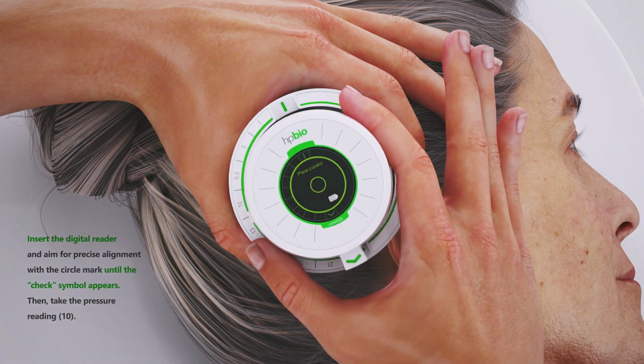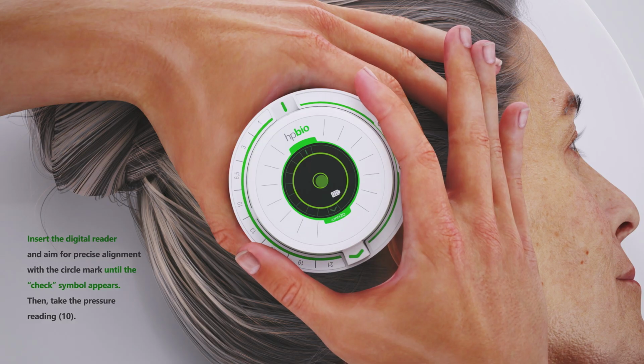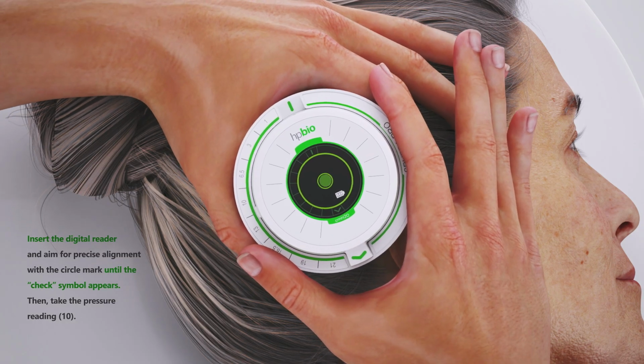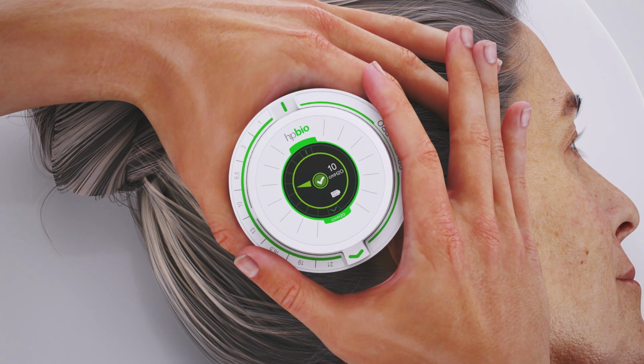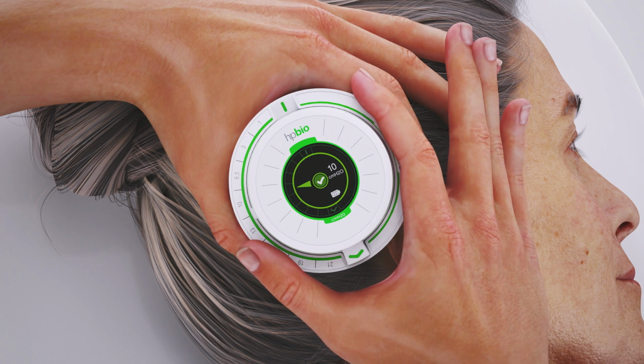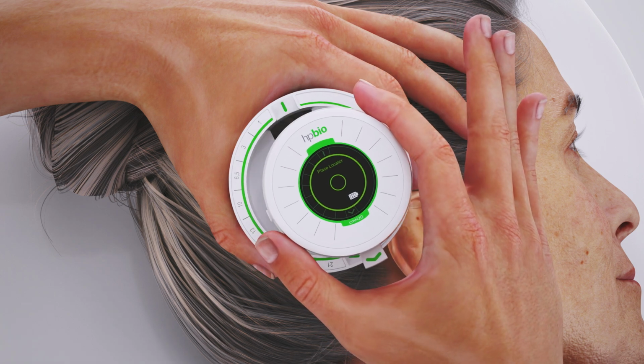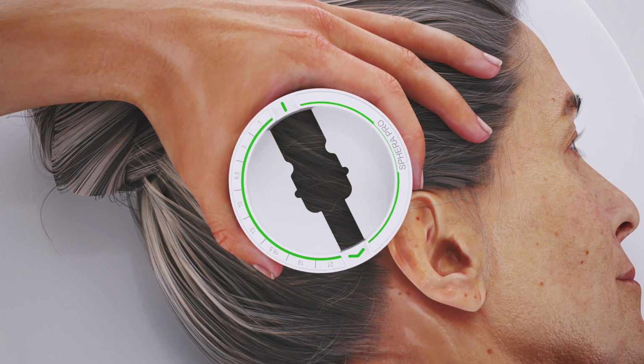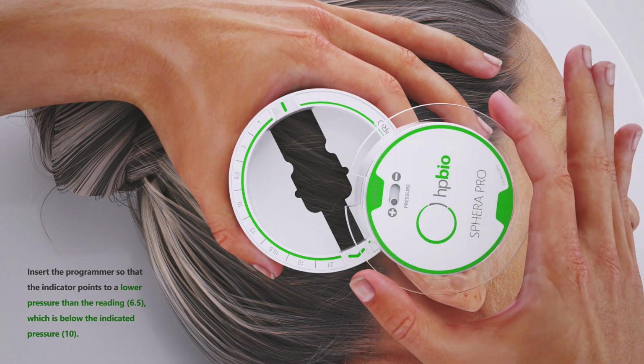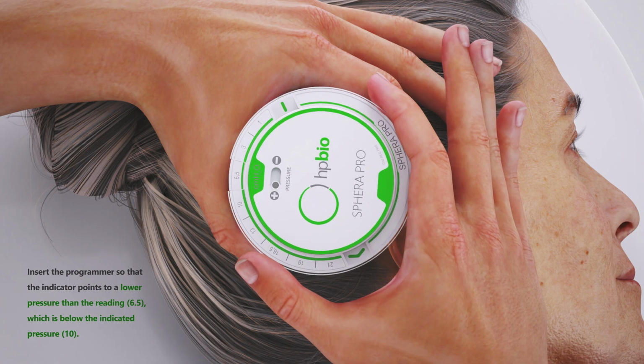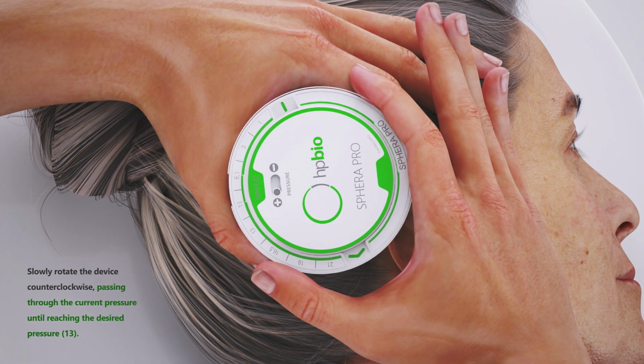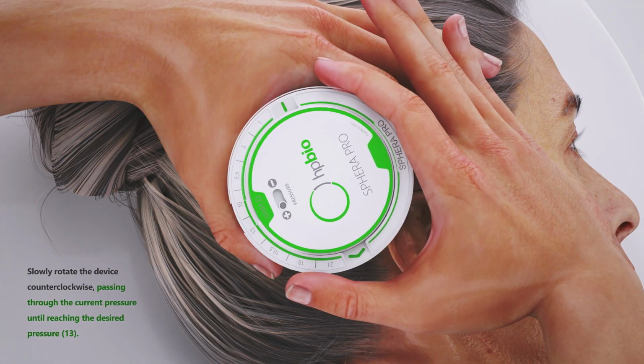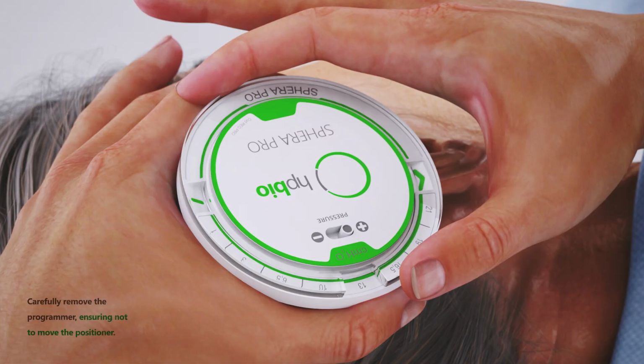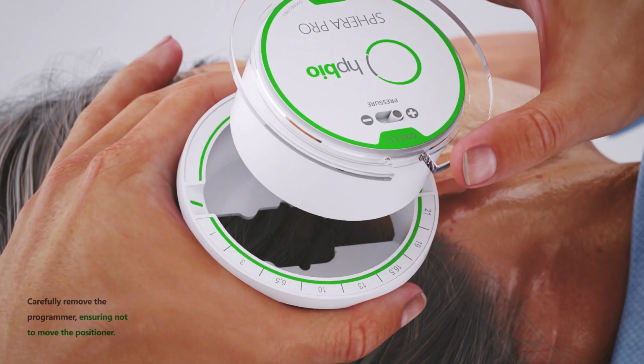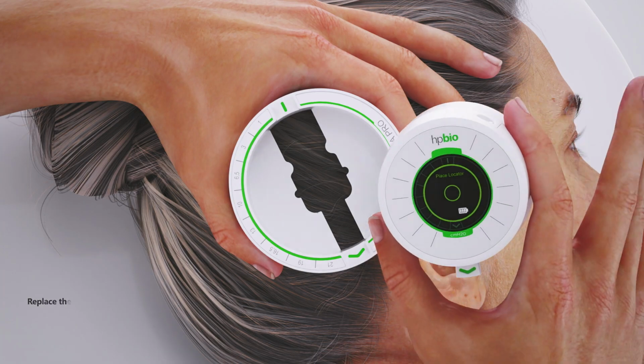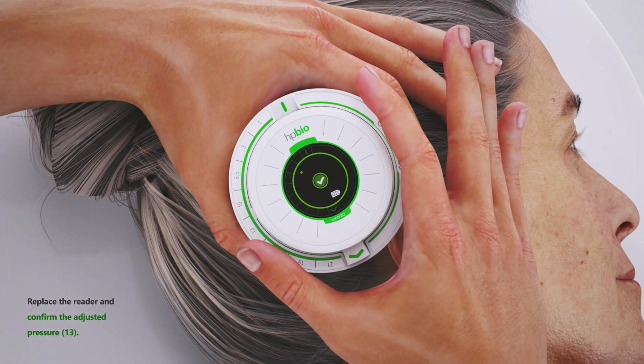Insert the digital reader and aim for precise alignment with the circle mark until the check symbol appears, taking the pressure reading. Carefully remove the reader, ensuring not to move the positioner. Insert the programmer so that the marker points to a lower pressure than the indicated reading. Slowly rotate the device counterclockwise, passing through the current pressure until the desired pressure is reached. Carefully remove the programmer, ensuring not to move the positioner. Place the reader again to confirm the new adjusted pressure.